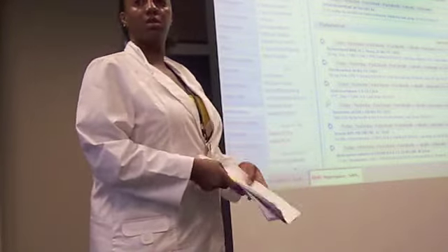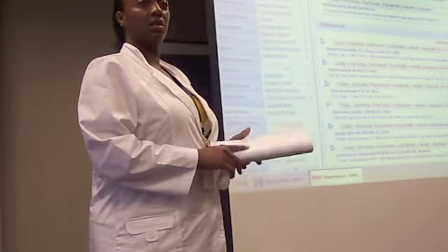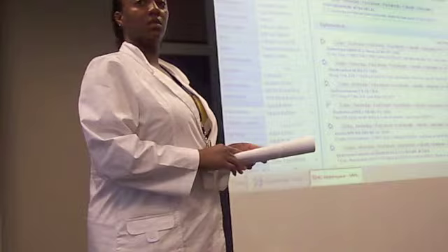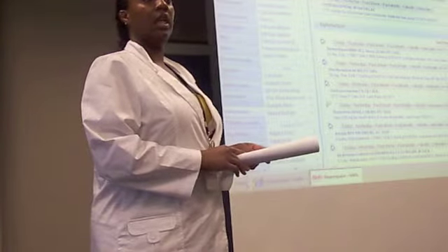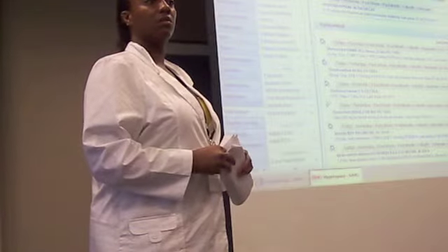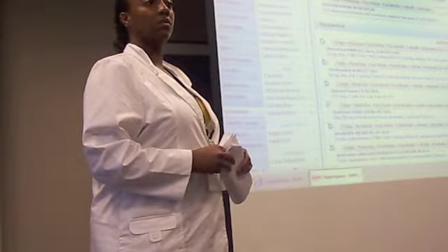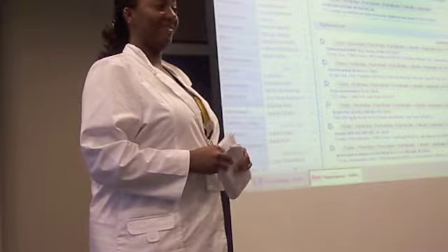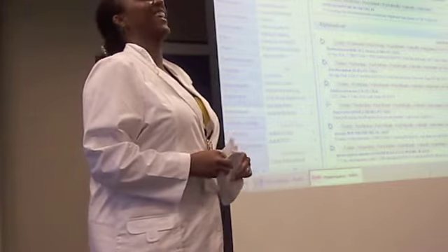The printout actually looks like a tele strip, the old-fashioned tele strip, not the Phillips generated one. So it's a string of paper, and they tear it and mount it on the paper. And they are supposed to write their name, why they interrogated the pump, and put the patient label on it. Every reader should do that, and I haven't seen that they have not done that. I really truly have not. Sometimes I can't read some of their writing, but they really do write on it. It's there, you just can't read it.